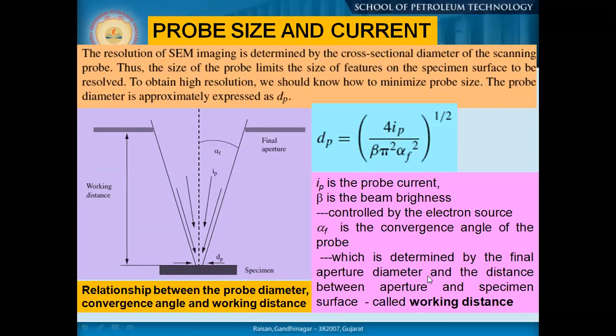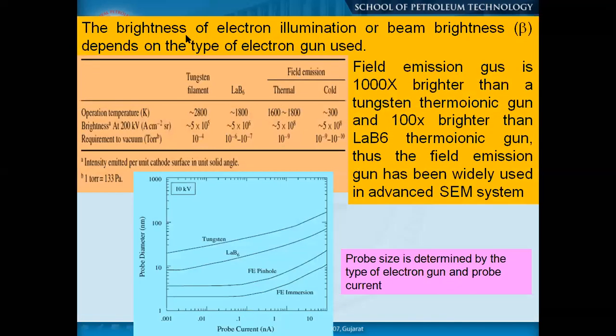The convergence angle is determined by the final aperture diameter and the distance between the aperture and the specimen surface, called the working distance. Depending on your source, your system, your aperture, and the specimen surface position, you can determine the resolution of your instrumentation.